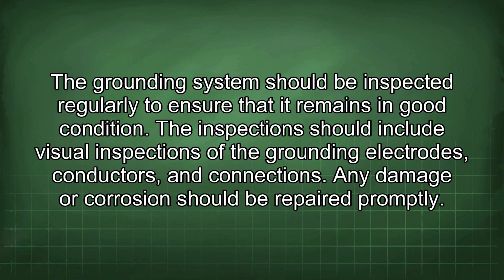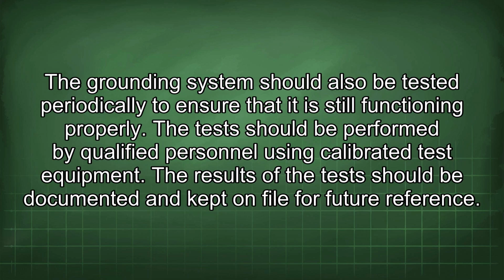The grounding system should be inspected regularly to ensure that it remains in good condition. The inspections should include visual inspections of the grounding electrodes, conductors, and connections. Any damage or corrosion should be repaired promptly. The grounding system should also be tested periodically to ensure that it is still functioning properly. The test should be performed by qualified personnel using calibrated test equipment. The results of the test should be documented and kept on file for future reference.